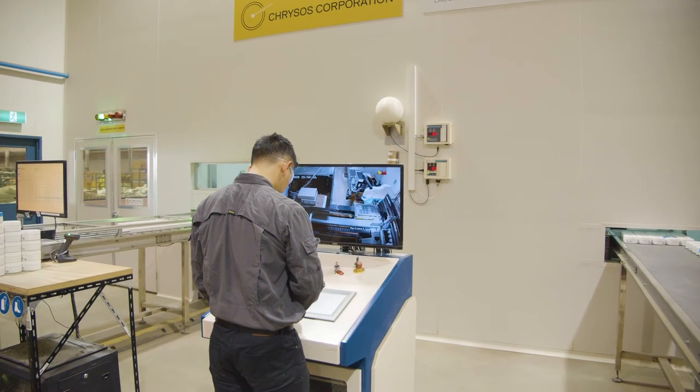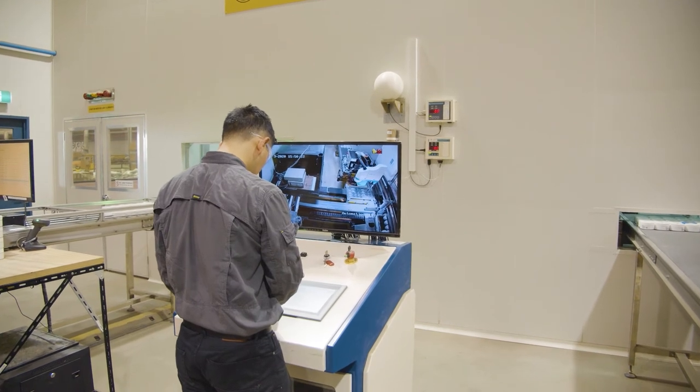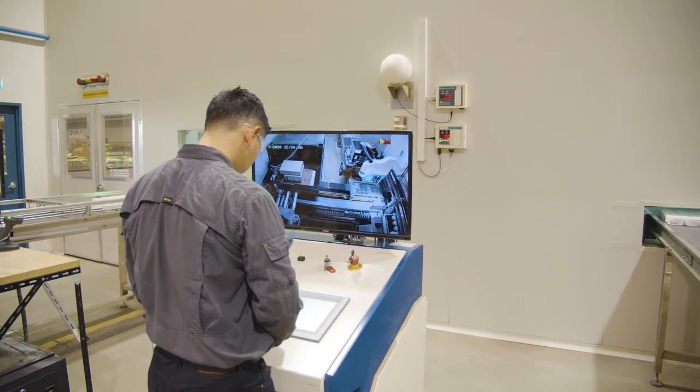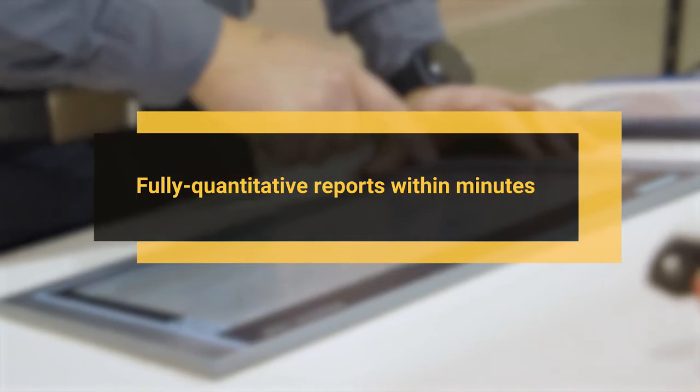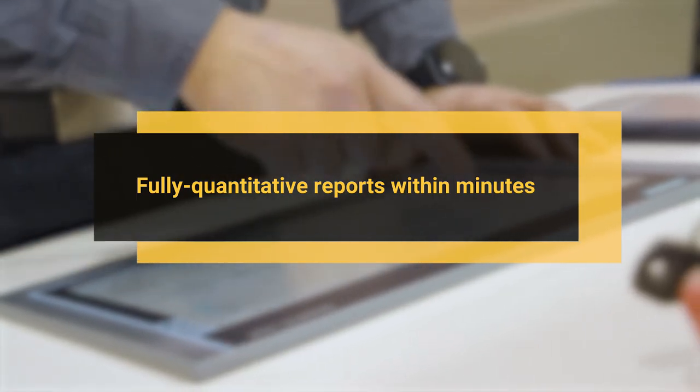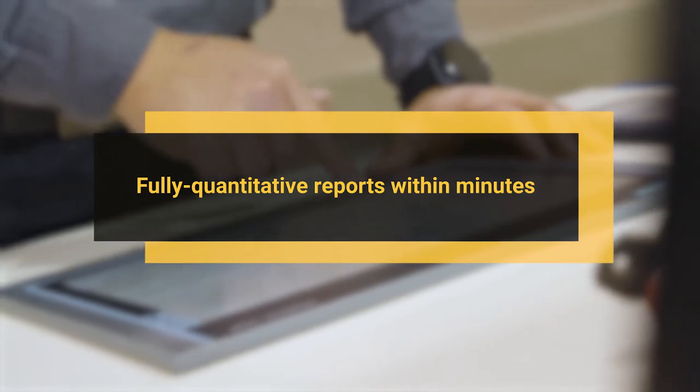Analysis reports are automatically generated when a batch is completed, or otherwise requested from the user interface software. This real-time QA-QC capability allows the operator to identify any issues immediately and reduce the chance of error. Reports are stored in a designated network drive location, shared with the laboratory information management system.